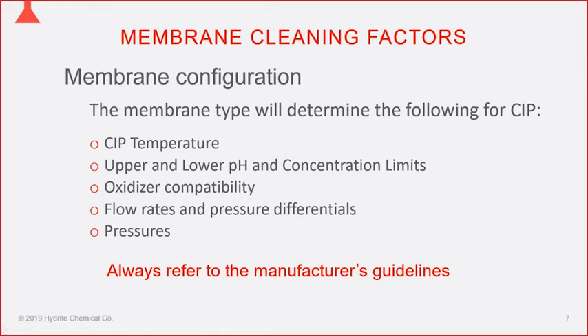Some membrane manufacturers tighten those limits, but generally the standard 2 to 11 range is the upper and lower target. Regarding oxidizer compatibility: the two most common oxidizers are sodium hypochlorite and hydrogen peroxide. Only MF and UF membranes can tolerate limited exposure to oxidizers. RO and nano membranes typically allow zero contact with oxidizers because they are thin film composite membranes very susceptible to oxidizer destruction.